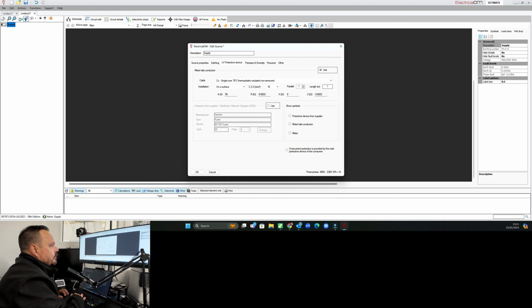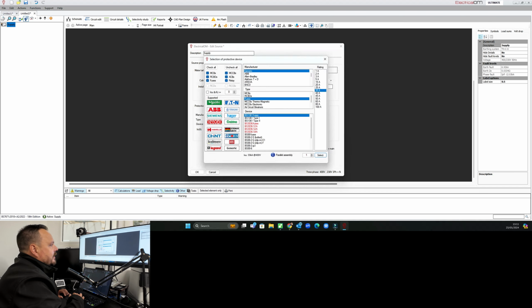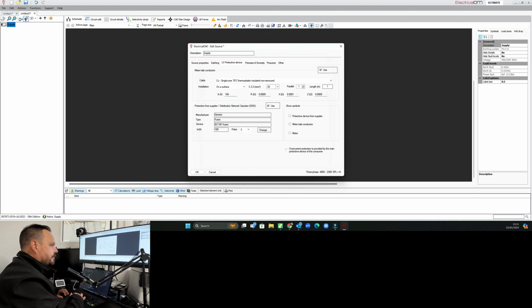We're going to use the tails on this as well. So we're going to again use the single core thermoplastic. We'll set them to 25 mil in size, about a meter long. We'll use the overcurrent protective device. It is just going to be BS1361 fuses, rated at 100 amps. We'll have the icons on there as well, because why not?